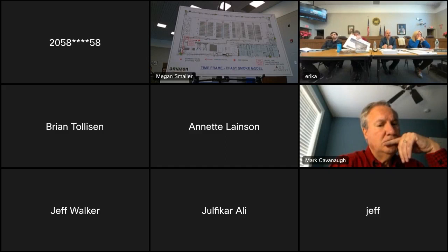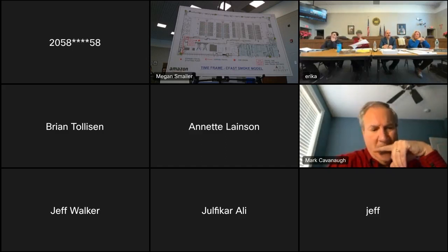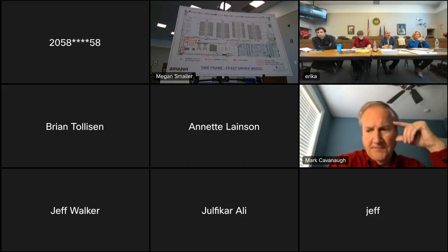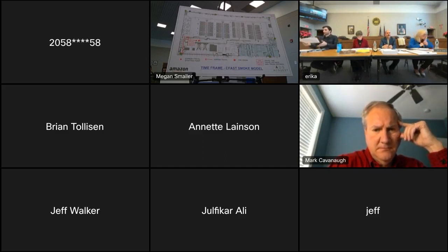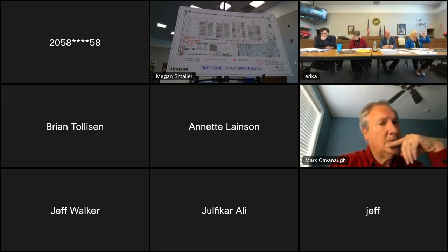So in this case, for this building, the driveway entrance, which comes on the southeast corner off of 9A, will come in at the first corner of the building, on the southeast side. Somewhere in that neighborhood is going to be that standpipe connection, because that's where the water main will be on the east side, going in from the fire tank and the pump, supplying water to the sprinkler system. So somewhere in that vicinity I'll have that standpipe connection close enough to a fire hydrant that we can hit it.